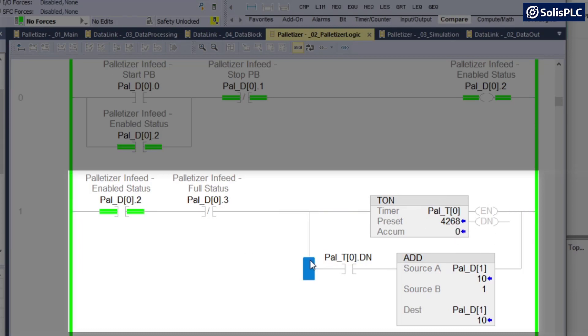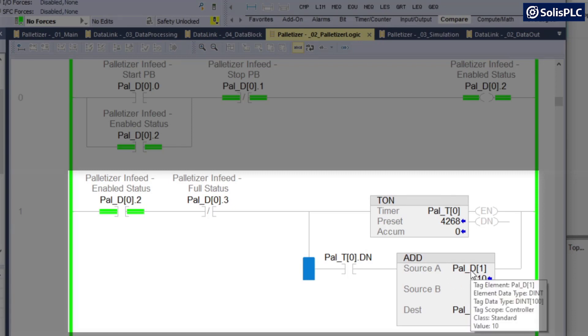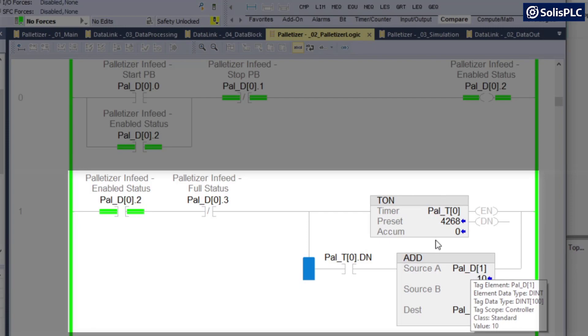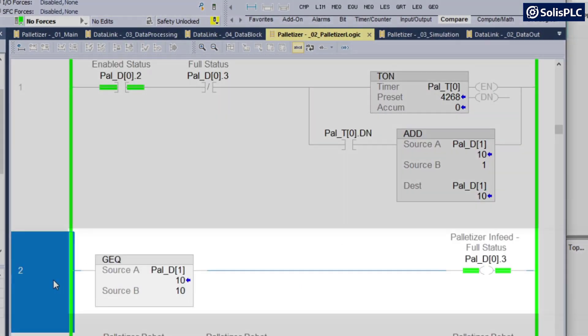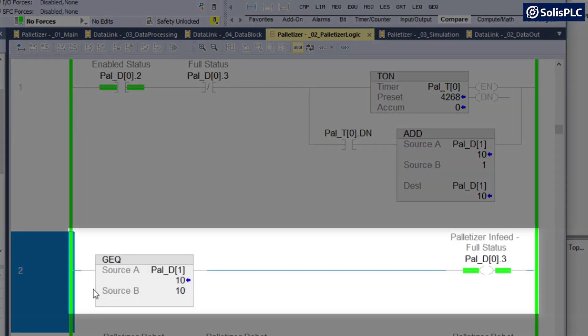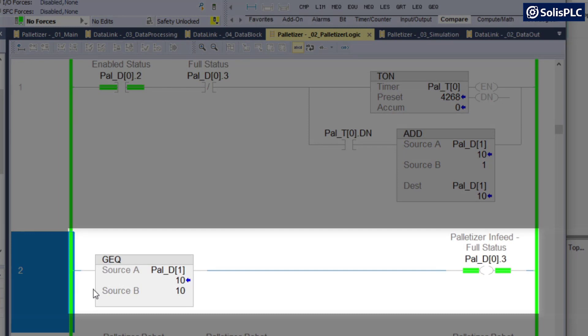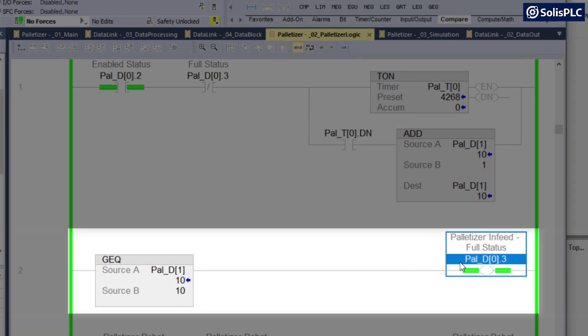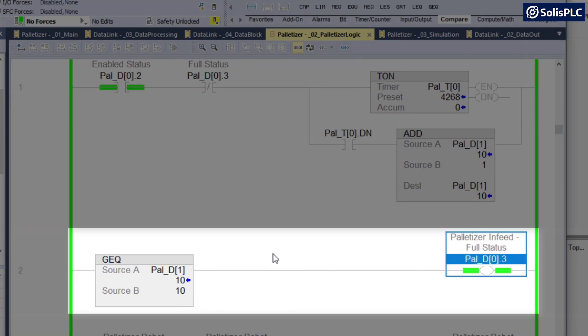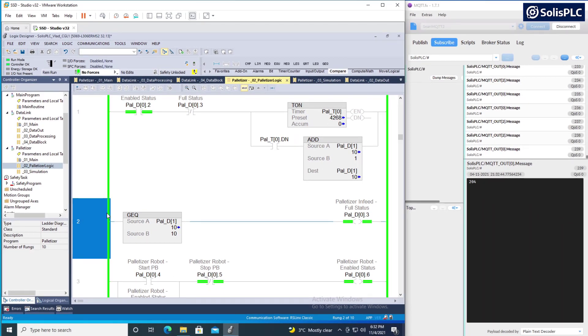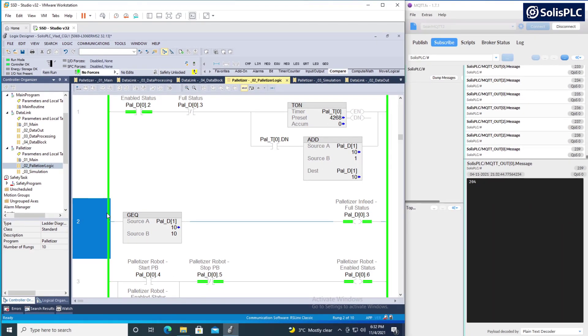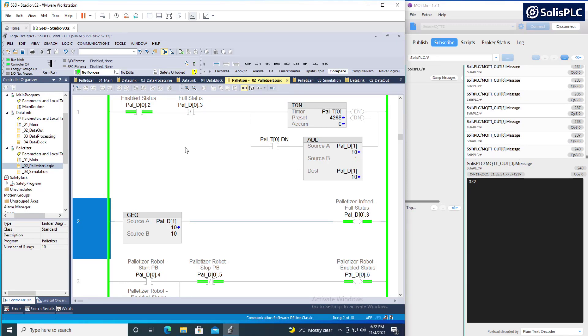Once this is done, you'll notice that we're going to increment this palletizer D1 register, which is going to count the number of boxes inside of the queue. Once the queue gets to 10, so this is a greater and equals than instruction, the palletizer is going to be deemed full using this bit. And once again, I just want you to look at this logic and see that this is something that you should be able to write once you've learned the base instructions of PLC programming. And this is something that I'm using to create some code that's going to be passing data into my broker.